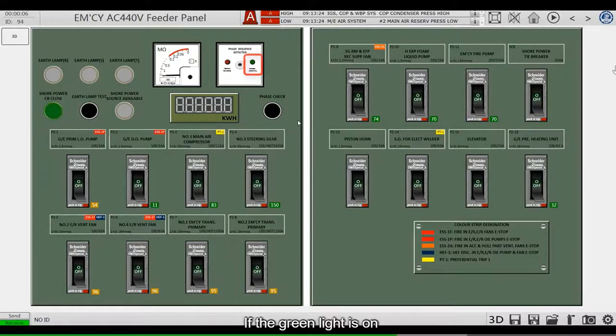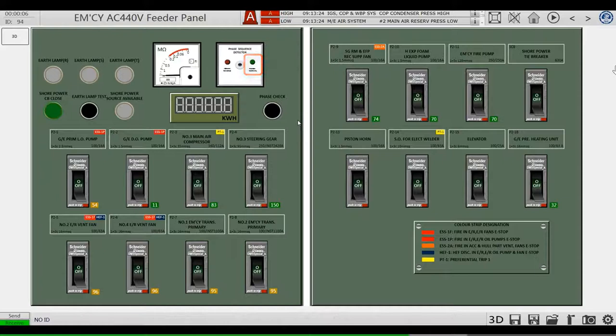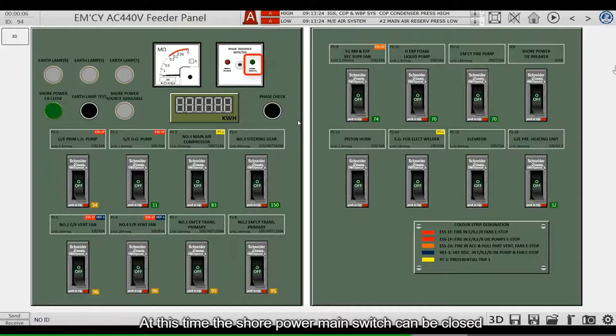If the green light is on, it means that the ship and shore electricity have the same phase sequence. At this time, the shore power main switch can be closed.